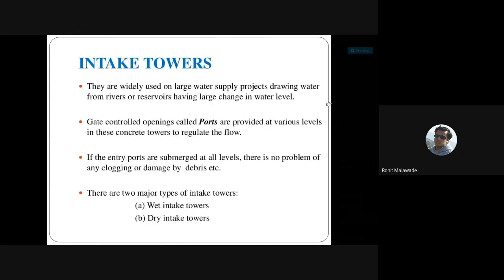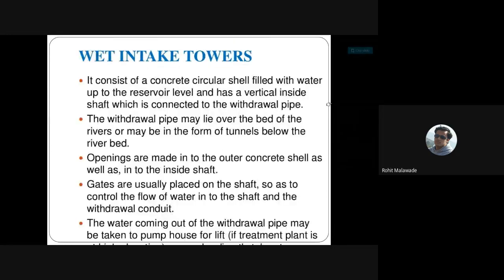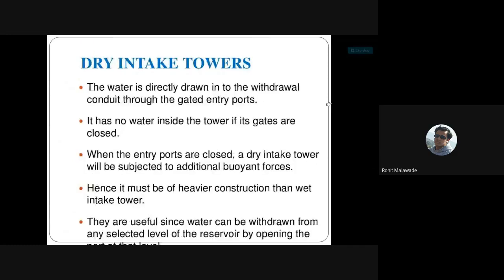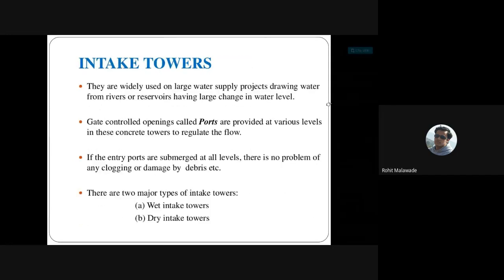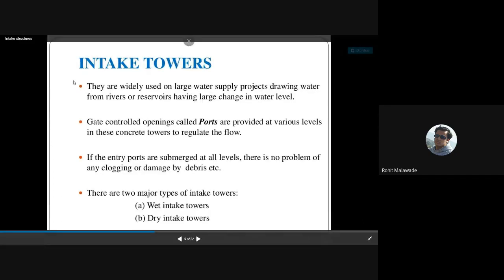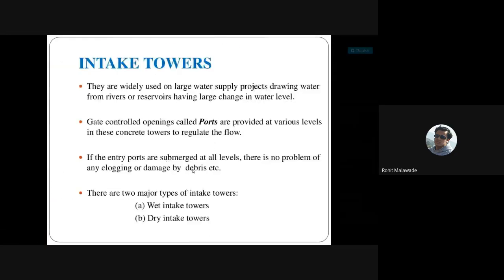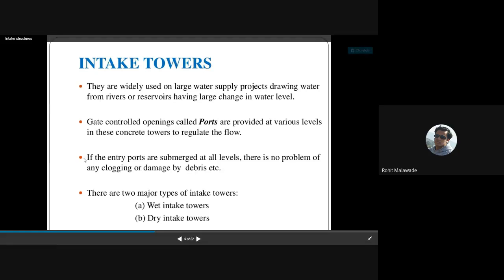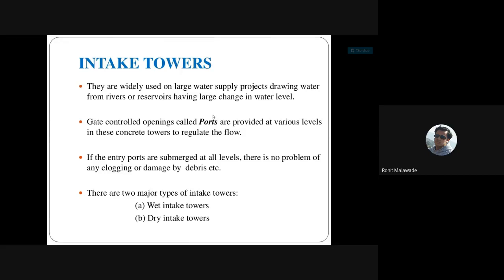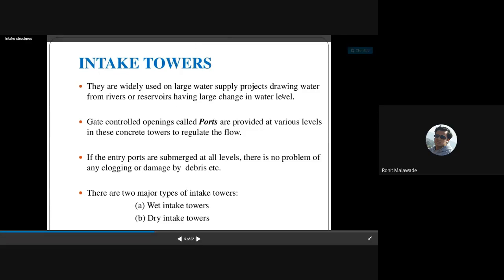Intake towers are widely used in large water supply projects to draw water from rivers and reservoirs. For a small water supply, a submerged intake is used; for large water supply schemes, intake towers are used. They have gate-controlled openings called ports provided at various levels in the concrete towers to regulate flow. If the entry ports are submerged at all levels, there is no problem of clogging or damage by debris.